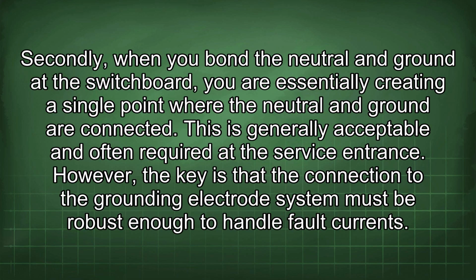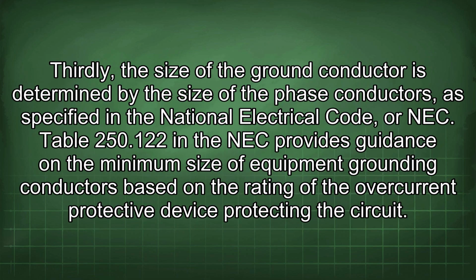Secondly, when you bond the neutral and ground at the switchboard, you are essentially creating a single point where the neutral and ground are connected. This is generally acceptable and often required at the service entrance. However, the key is that the connection to the grounding electrode system must be robust enough to handle fault currents. Thirdly, the size of the ground conductor is determined by the size of the phase conductors, as specified in the National Electrical Code, or NEC.